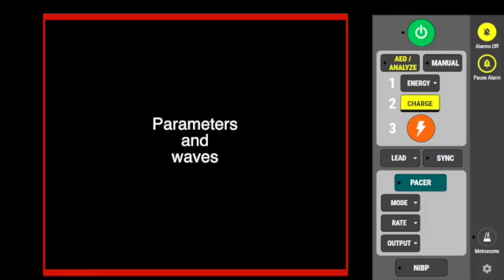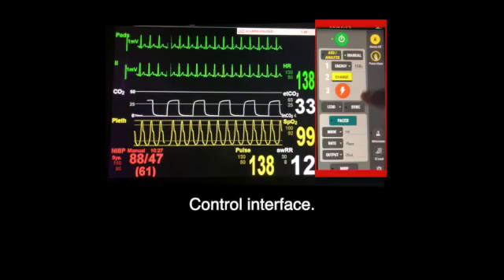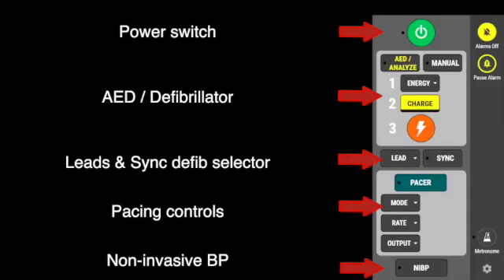Parameters and waveforms can be found on the left. At the right is the control interface, including the power switch, AED or defibrillator selector, leads and synchronized defibrillator selector, and pacing controls.